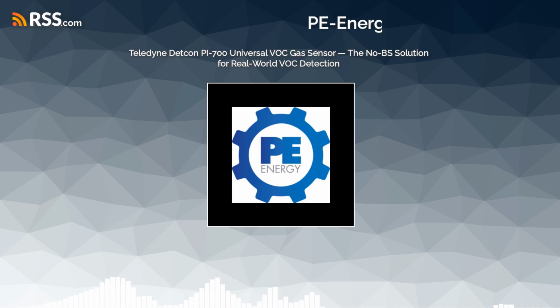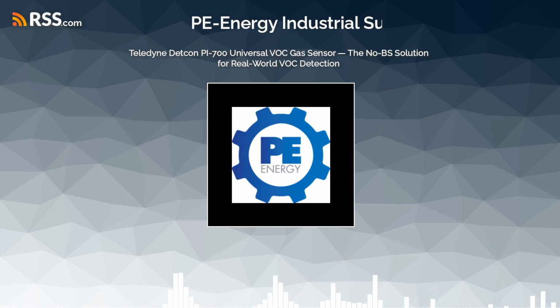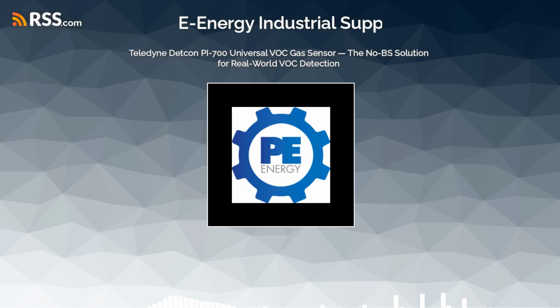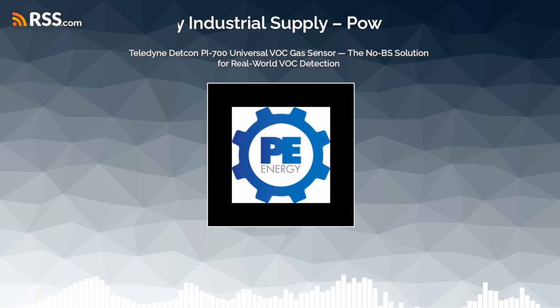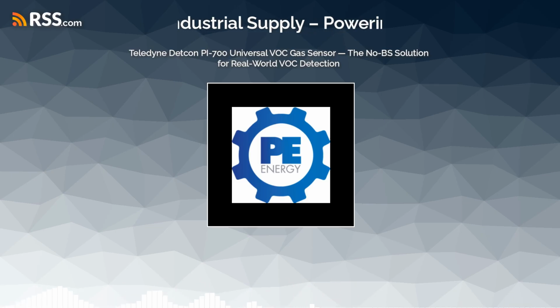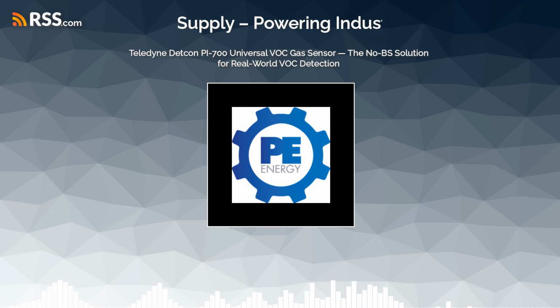So detecting it usually involves an electrochemical sensor that is, by its very nature, being chemically attacked by the gas it's trying to detect. Oh, wow. So a 1.5-year lifespan isn't a manufacturing defect, it's just the cost of doing business with fluorine. Exactly. The sensor is actively sacrificing itself to give you that reading. If you ever see a manufacturer claiming a 10-year life on a fluorine sensor, you should be very, very skeptical. The PI-700 specs are just being honest here. They reflect the harsh reality of the chemistry.